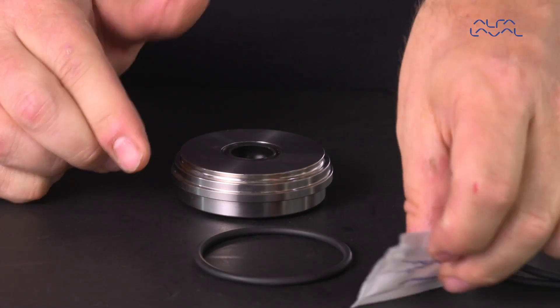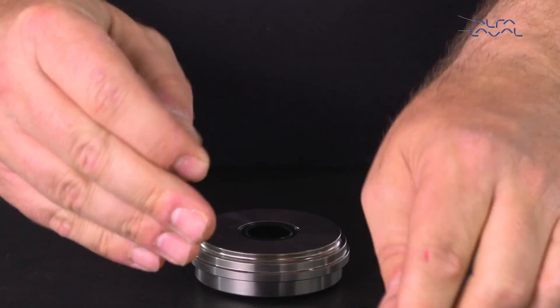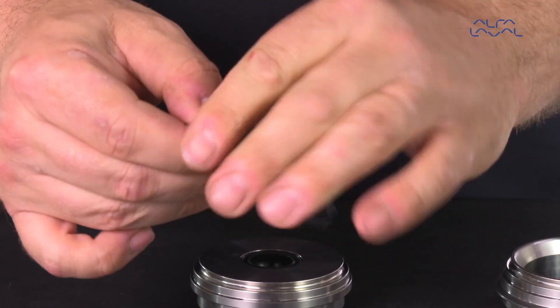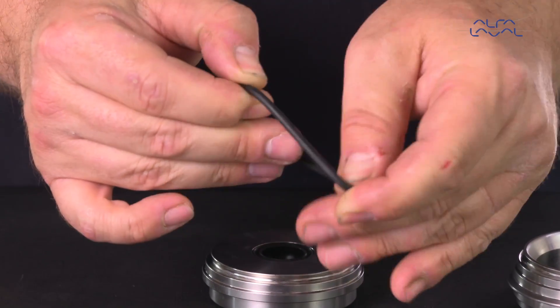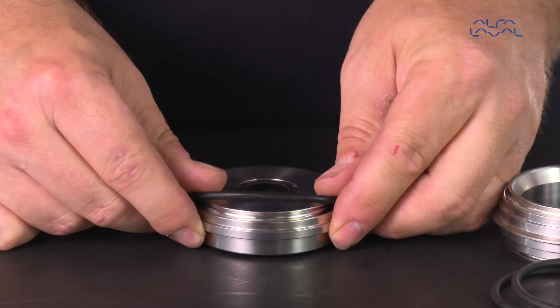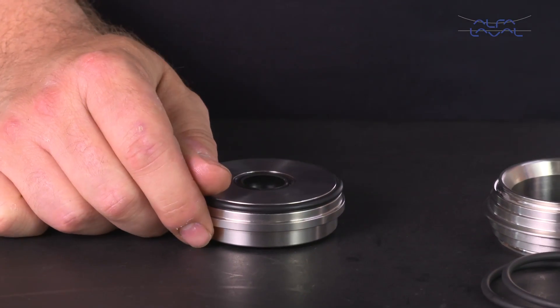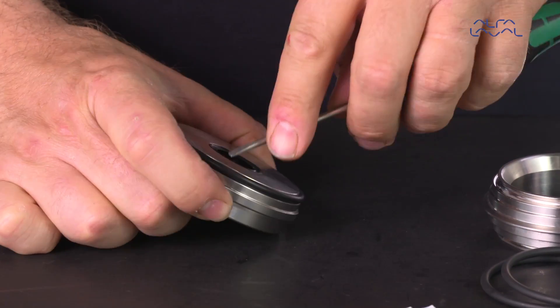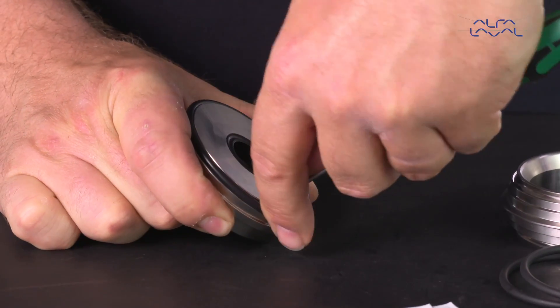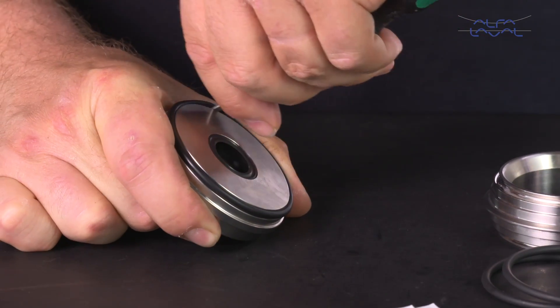Next, lubricate and mount the body o-ring onto the sealing element. Carefully place a small screwdriver on the backside of the o-ring and turn it 360 degrees to ensure that the o-ring did not twist or roll during installation.